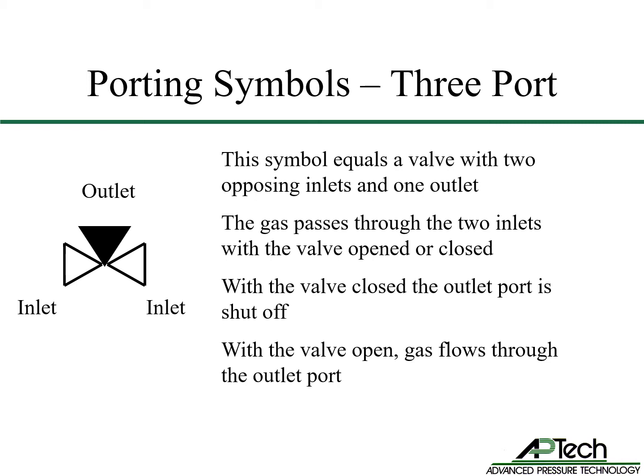Three triangles represent a three-port valve. The image on the left is a valve with two inlet and one outlet ports. The two inlet ports — the open triangles — are common; gas flows through if the valve is open or closed. When the valve is closed, the solid triangle outlet port is shut off. When the valve is opened, gas flows through the outlet port.